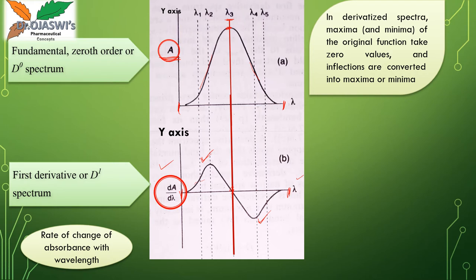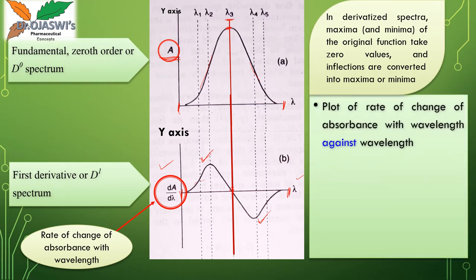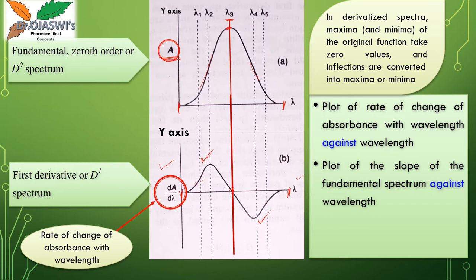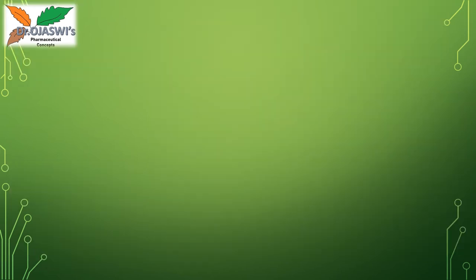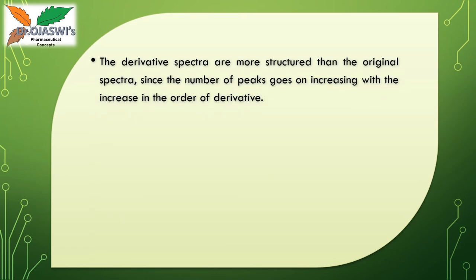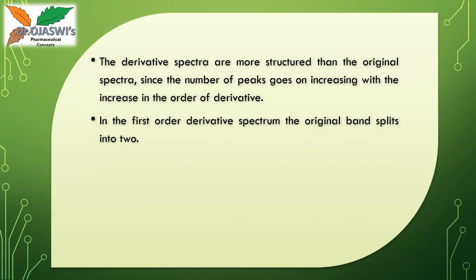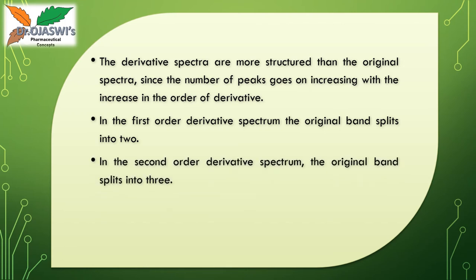In the first derivative spectrum, the rate of change of absorbance with wavelength is plotted on the y-axis — it is a plot of dA/dλ against λ, or the slope of the fundamental spectrum against wavelength. The derivative spectra are more structured than the original spectra since the number of peaks increases with the order of derivative. In the first-order derivative spectrum, the original band splits into two; in the second-order, it splits into three.